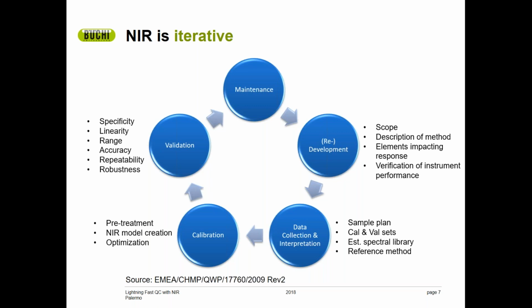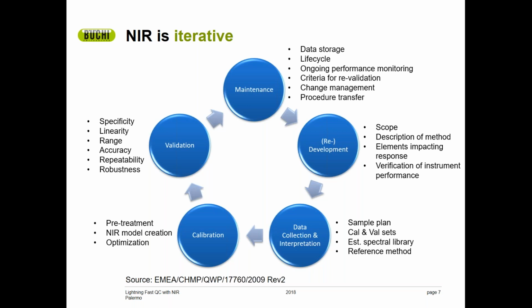The life cycle of a calibration does not end with the start of routine use. Performance of the method should be monitored routinely and updated with samples that demonstrate new sources of spectral variation, maybe things like particle size or compositional variations as they occur. When new samples are identified to augment an existing calibration, you run through the loop once again.